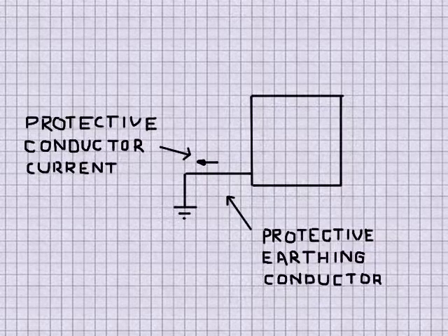Although we tend to think of the ground wire as a protection just in case, when the specified insulation fails and for some reason the user may be exposed to mains voltages, the IEC specifies what they call protective conductor current, which is the current flowing through the protective earthing conductor, that is the ground wire, under normal operating conditions. This means that they admit that some devices need the ground wire connected at all times to offer adequate protection. That is the case of our shower head.